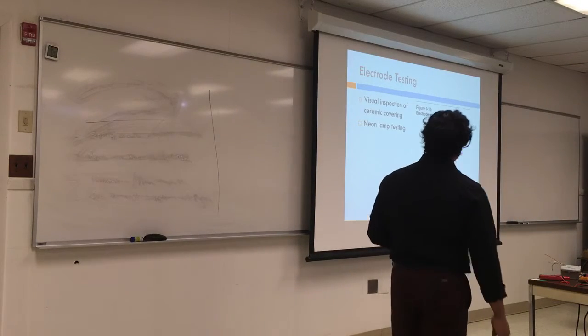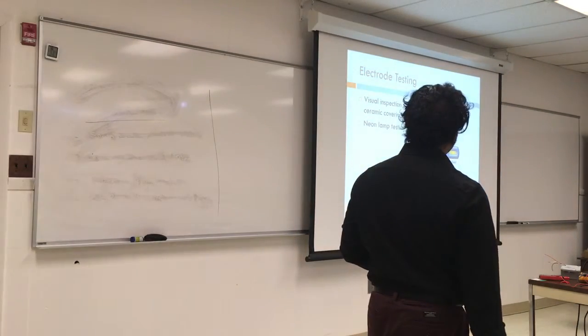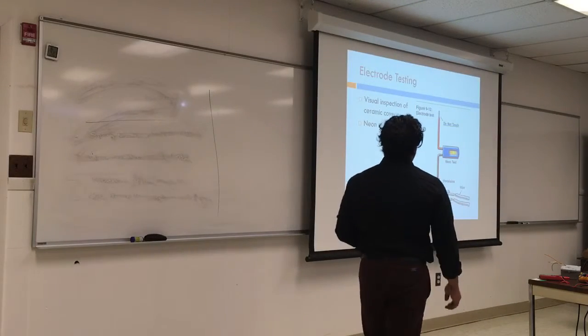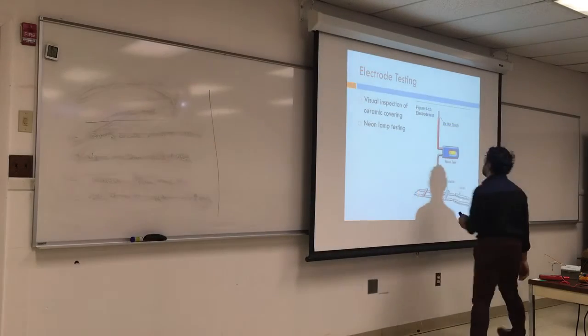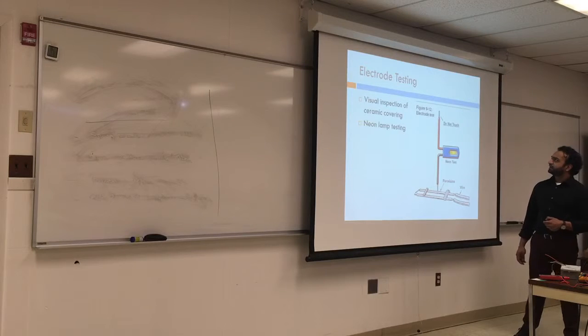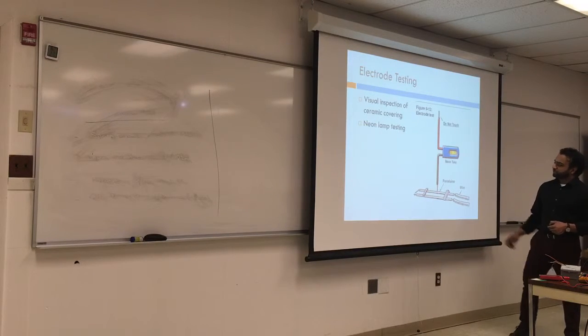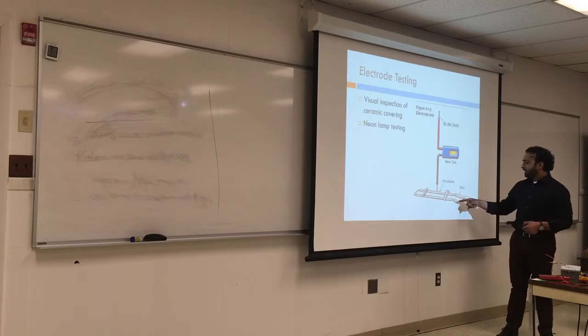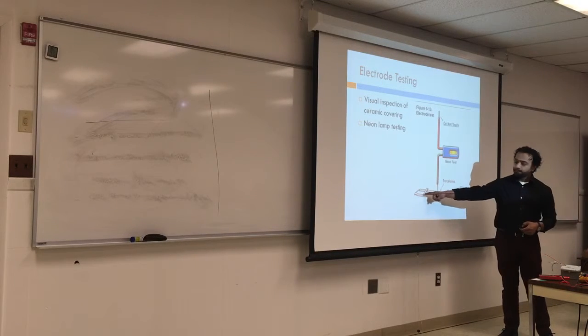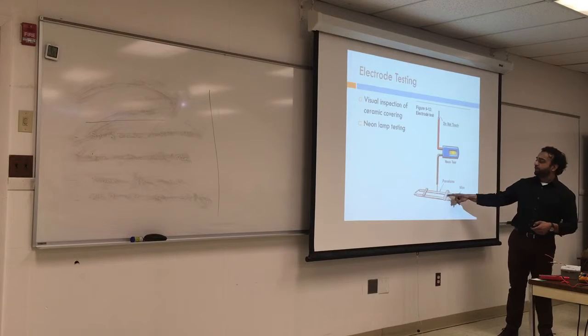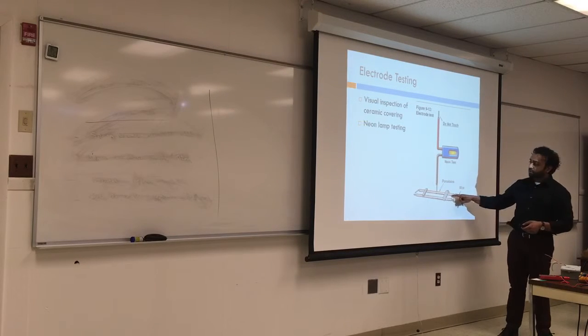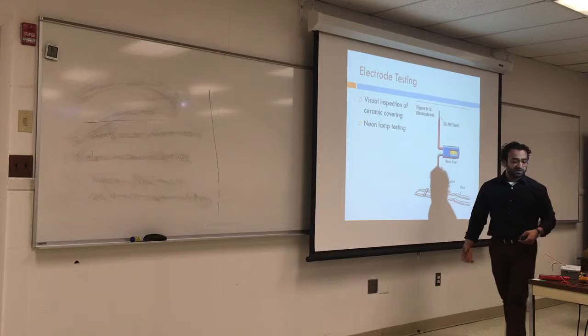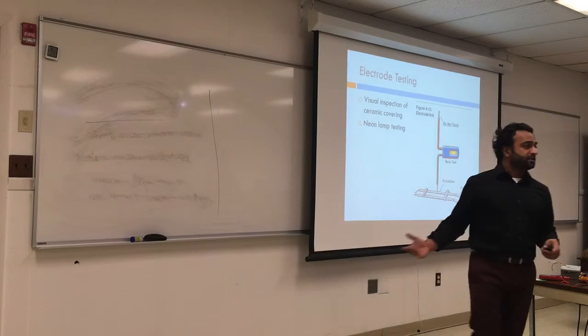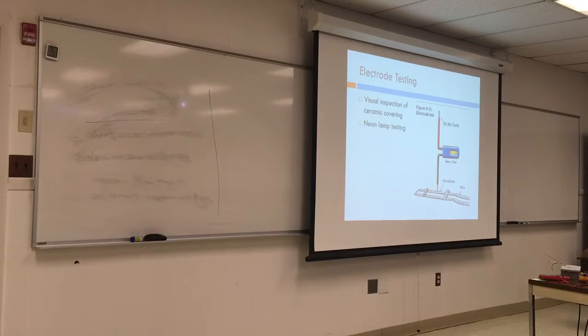This is an old way to test for leaks. I've seen this before, but I never used it, and I highly doubt you will need to use this sensor to sense if there's any leak from the porcelain. And if you notice, those leads are very long. Probably they're a little bit expensive, so you want to test if they are leaking or not. But they're not that expensive, so it's better to just change the electrodes if you're in doubt that they are cracked. What do you think will crack the ceramics?